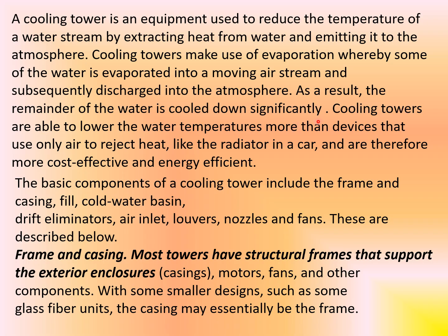Cooling towers are able to lower the water temperature more than devices that use only air to reject heat, like the radiator in a car, and are therefore more cost-effective and energy efficient. The basic components of cooling tower include the frame, casing, fill, cold water basin, drift eliminators, air inlet, louvers, nozzles and fans.